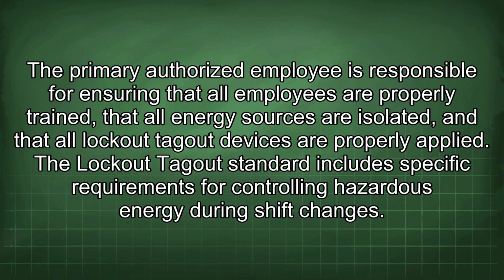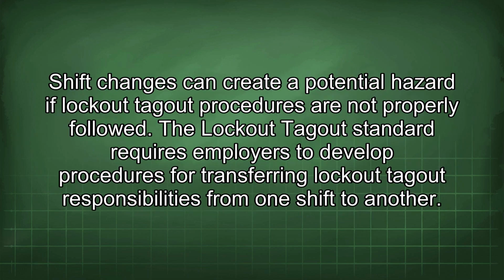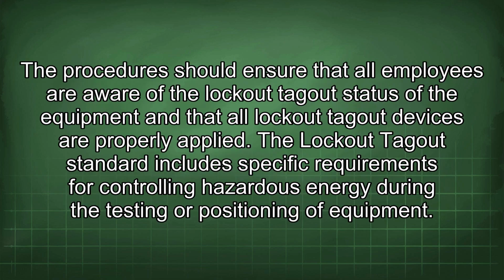The Lockout Tagout standard includes specific requirements for controlling hazardous energy during shift changes. Shift changes can create a potential hazard if Lockout Tagout procedures are not properly followed. The Lockout Tagout standard requires employers to develop procedures for transferring Lockout Tagout responsibilities from one shift to another. The procedures should ensure that all employees are aware of the Lockout Tagout status of the equipment and that all Lockout Tagout devices are properly applied.